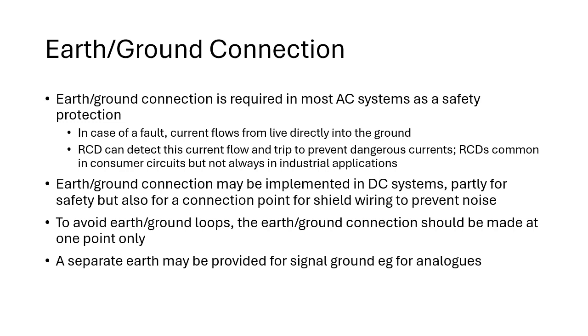Not required so much for 4 to 20 milliamp loops, because typically with 4 to 20 milliamps you use a single twisted pair, 2 wires, and then any noise received by one wire is also received by the other wire, and it cancels out. But for DC circuits, if you want to protect against noise, it's very common to use a shield. Also for thermocouples and RTDs, they may well need shielding as well. So that earth or ground connection can be used to prevent noise or to dissipate noise, as well as for safety.